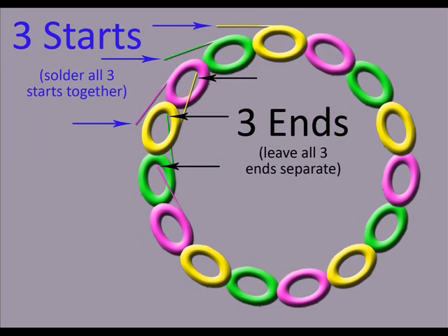The result is three sets of connected coils, each with one starting wire and one ending wire. The starting wires are then soldered together, thereby connecting all three phases, and leaving a total of three ending wires. This wiring technique is called Series Star.